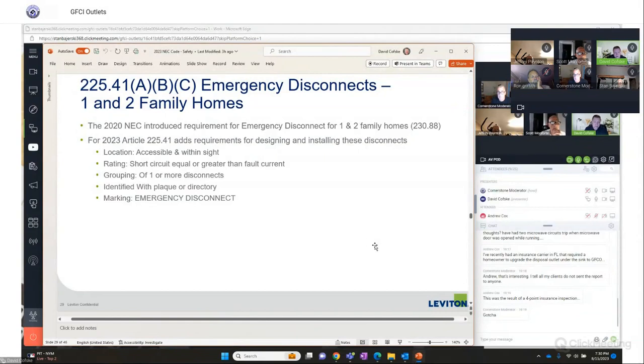The other thing within code under 225.41 is basically any new house needs to have an emergency disconnect, single and two family homes. So basically, if you're in a house, that's fine. But as soon as you change something out on the outside of the house, you need to now have an emergency disconnect. The real purpose of that is if there's an emergency at your home, like a fire, instead of the fire company coming up and cutting wires, they want to be able to shut your house off from the outside. And that's really what's driving that.